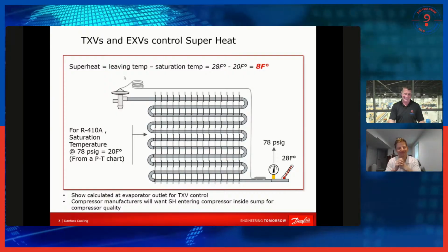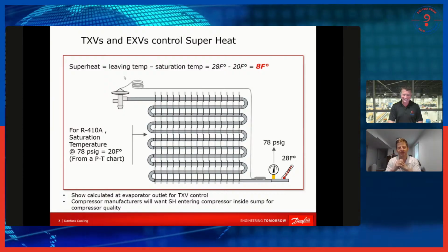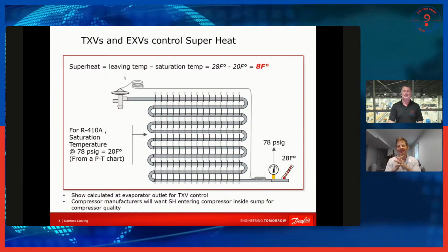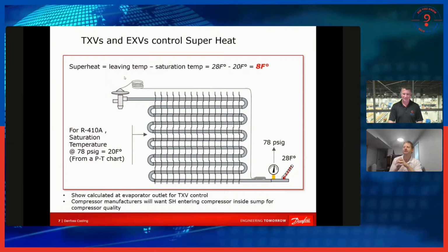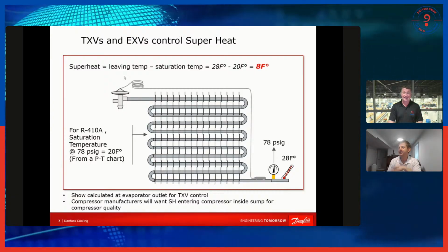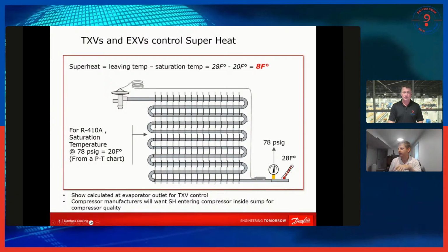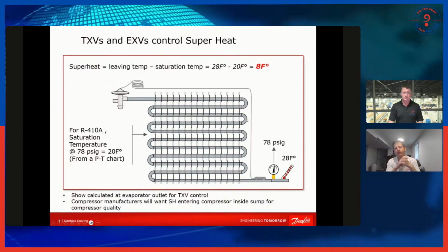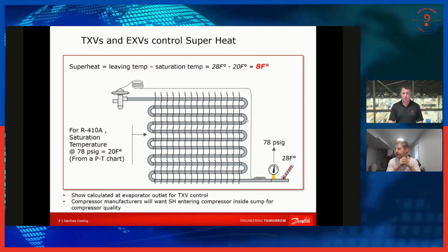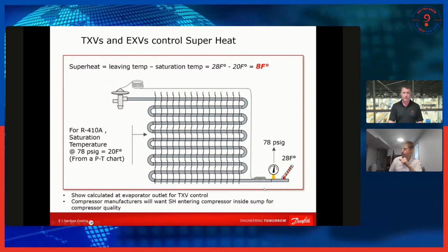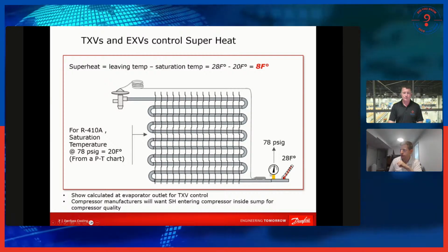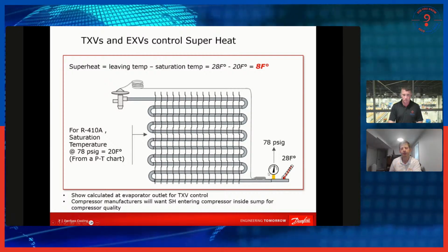Yeah, and that always leads to the question, okay, and what value is good? Here it's an example, 8 degrees superheat leaving an evaporator, and you calculate that the same way whether it's a TXV or EXV. Ideally, when you're measuring superheat, you want to get as close to the evaporator as possible.